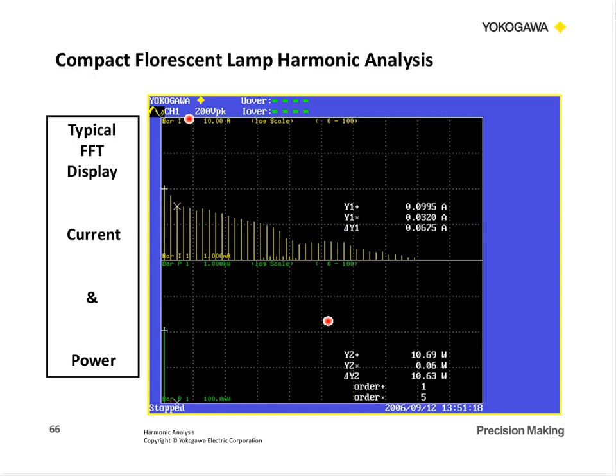So here we can look at the power, and this is what I was saying. The power harmonics go away, and it's very hard to see, but there's a little red blip right down here at the bottom, about the third order. That shows a negative power. So because of the harmonic phasing, we actually have a harmonic that's going in the reverse direction on that lamp. So those are things that we can see.